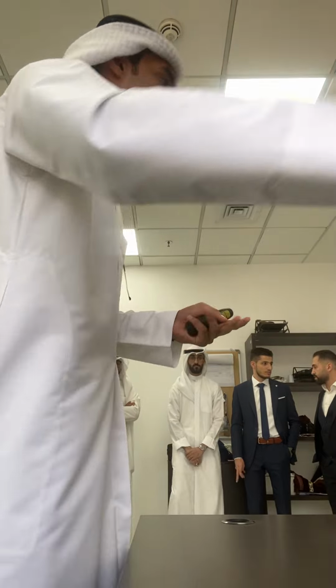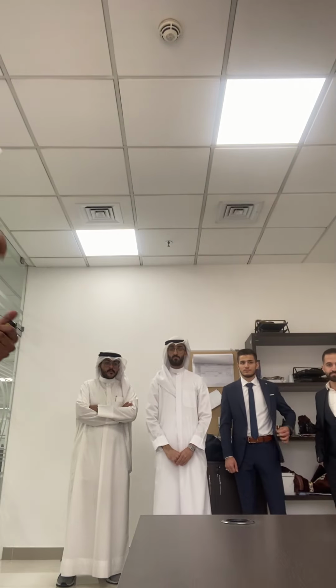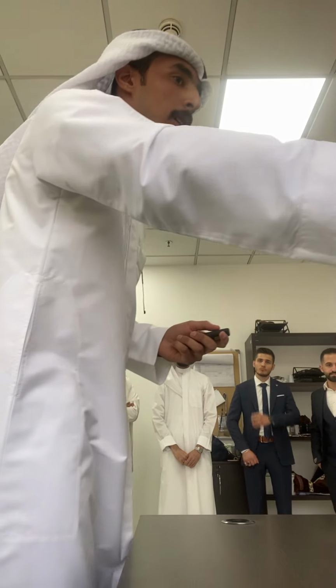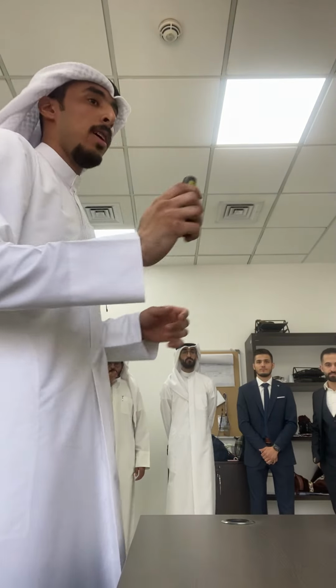Then we have the appliances, so if there is a coffee machine or food warmer, the heat will be more. Then we have the Q sensible and the Q latent for the ventilation. After that, we have to sum all of these heats to get the total heat, the cooling load. This part is the hand calculation. Then we did the same for our room in the HAP analysis, HAP software.